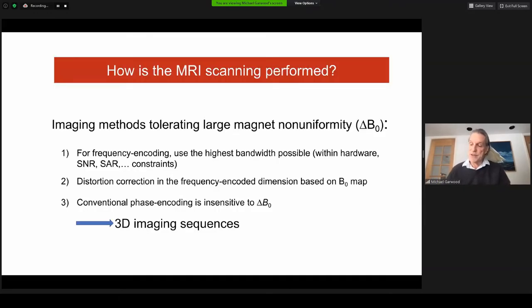Now let me briefly describe the methods employed to image with extremely non-uniform magnetic field. For frequency encoding, we will use the highest bandwidth possible within certain limits to minimize field-dependent image distortion. The remaining image distortion in the frequency-encoded dimension is corrected in post-processing using the known magnetic field profile. Spatial encoding in the other two dimensions of the 3D image is done with phase encoding, which is insensitive to magnetic field inhomogeneity.